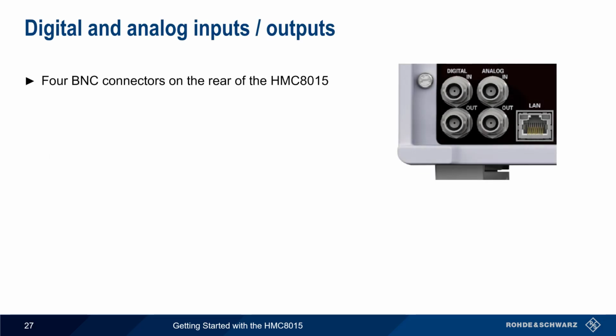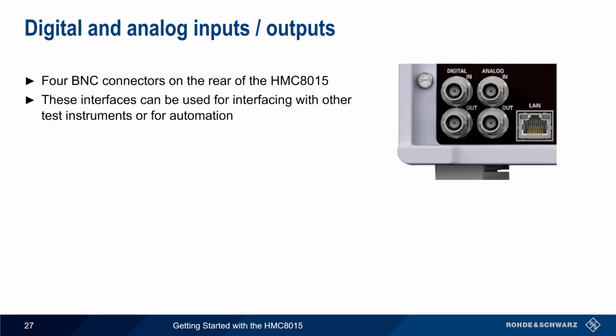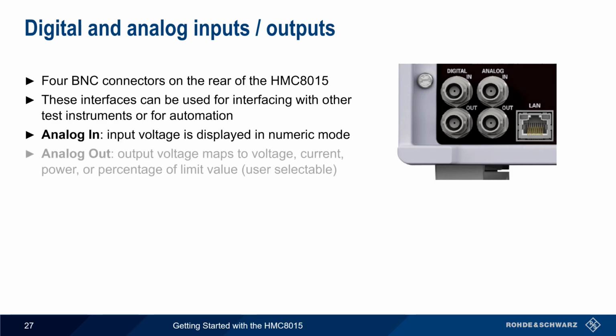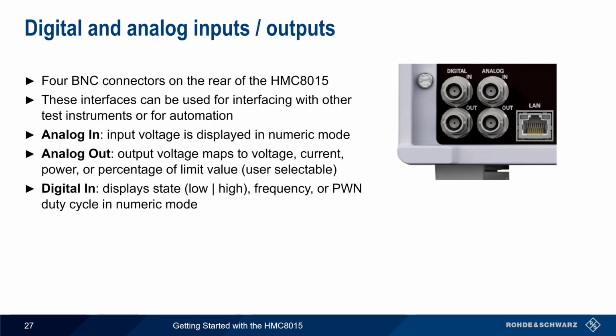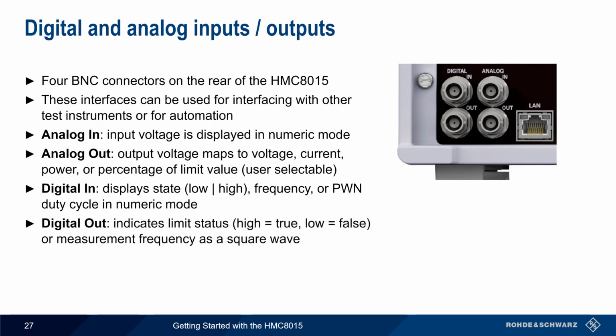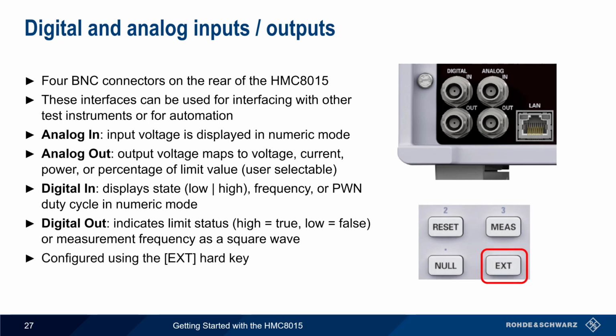The rear panel of the HMC8015 has 4 BNC connectors that can be used for interfacing with other test instruments or for automation. The analog in connector measures an external voltage input and displays this value in numeric mode. The analog out connector produces a voltage which maps to a user-selected measurement value on the HMC. For example, voltage, current, or percentage of limit value, as described just a moment ago. The digital in connector can be configured to display whether the input is high or low, or the frequency or duty cycle of an external pulse width modulated signal. And digital out can be used to either indicate a passing or failing limit value, or it can output the measurement frequency in the form of a square wave. The external hard key is used to configure the behavior of these inputs and outputs.